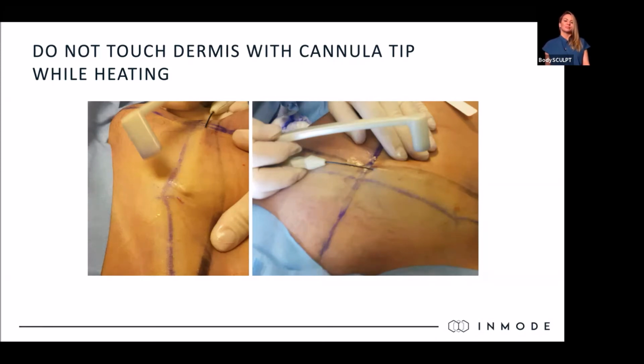But water is your friend for the following reasons, in my opinion. Number one, it ensures that you have a safe distance between the tissue and the undersurface of the probe. We're going to keep harping on that. Number two, water acting as a heat sink, because it has a high specific heat, will also distribute the heat energy secondarily. So you get a direct RF effect, and then you get a secondary heat effect from the surrounding tissue and fluids, mostly the water getting heated, and you're going to get collagenesis from those two things.